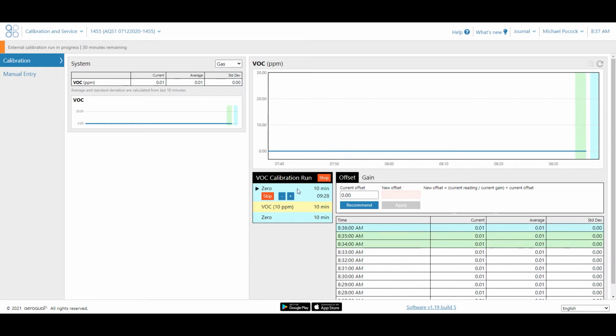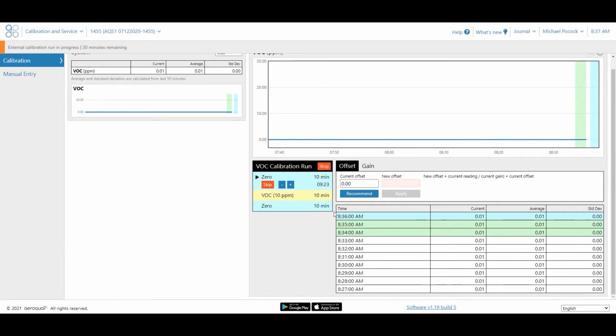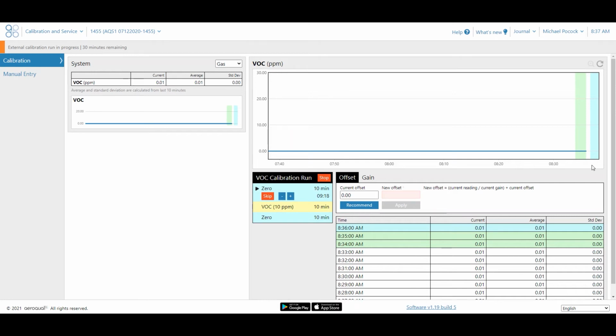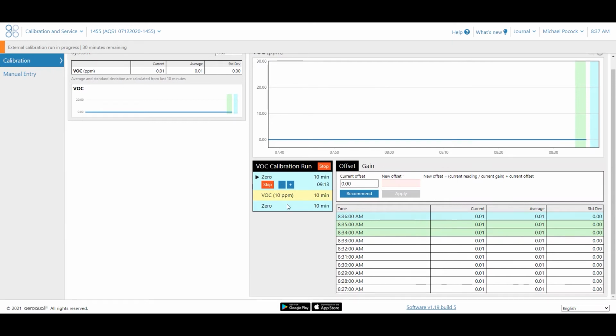So have a look at this box. What is this box here? This is the last 10 readings, and this box up here is just showing you a graphical version of that. So what you can see here, I've been feeding it zero air for a while, and it's very constantly giving me a reading of 0.01. Okay, so that is within the tolerance for this monitor and this calibration. So you wouldn't really need to make any changes here.